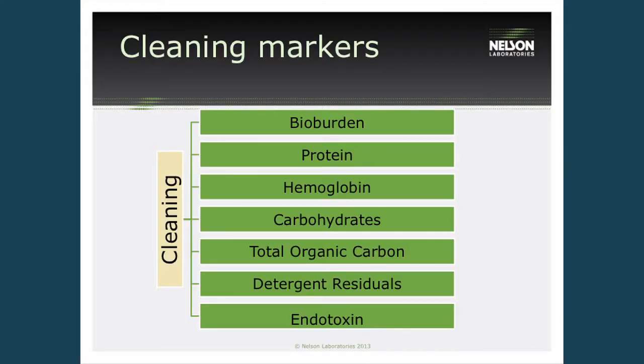So there's a lot of different options to test when making sure medical devices are free and clear of anything after the cleaning process. We can test this by using bioburden, so testing for any organisms. So we'll put the organisms into the test soil, then we'll test for them at the end of the process. We can also use this by testing protein, hemoglobin, carbohydrates, total organic carbon, detergent residuals, making sure we're rinsing properly, and also testing for endotoxin. Now, all these types of markers, we need to ensure that we put these on the device first of all. So that would determine what test soil we're utilizing and that sort of thing.